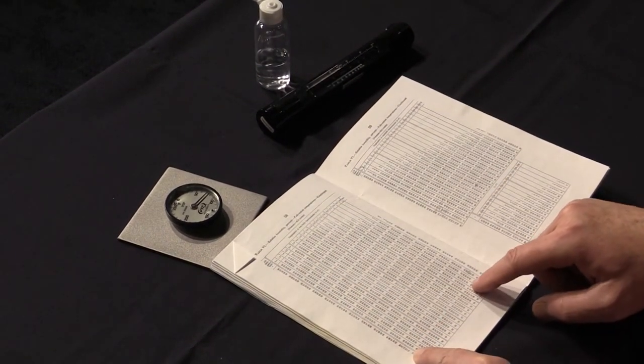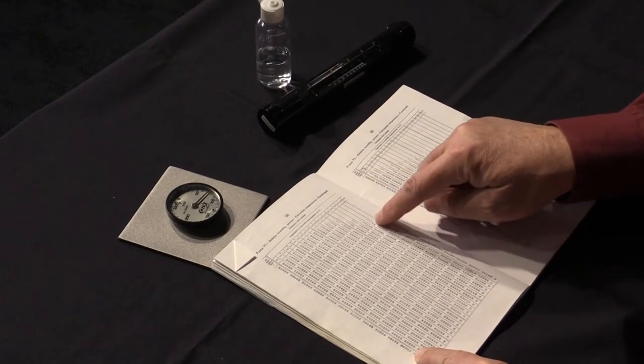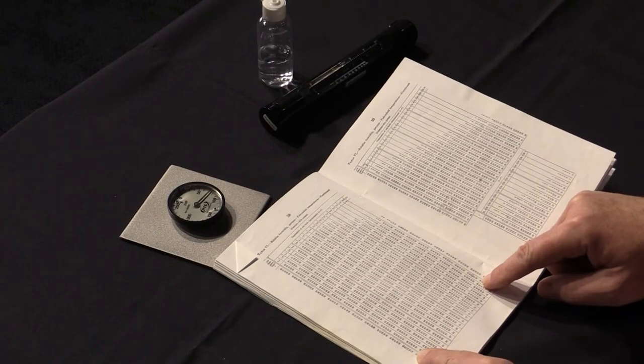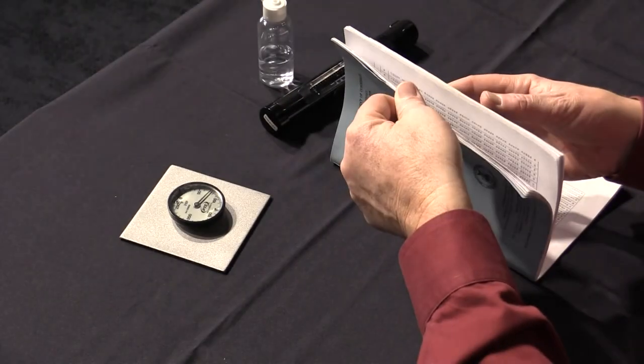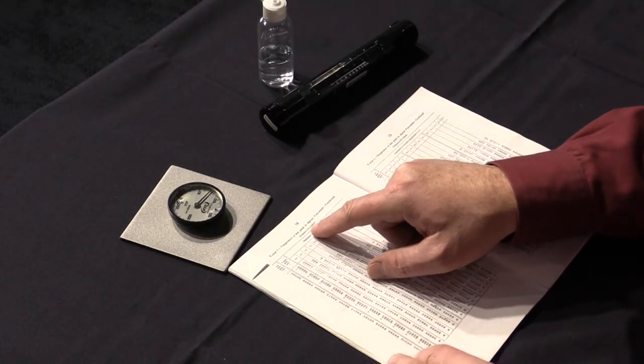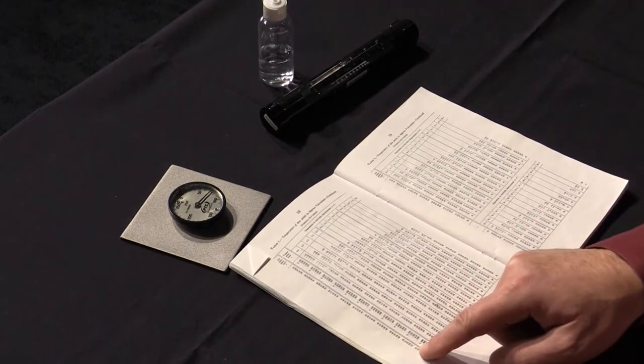Locate the psychrometric chart for relative humidity corresponding to the barometric pressure in the work area. We'll use the 30 inch table. Intersect the air temperature with the difference between the wet and dry bulb temperatures to determine the relative humidity and record that value.